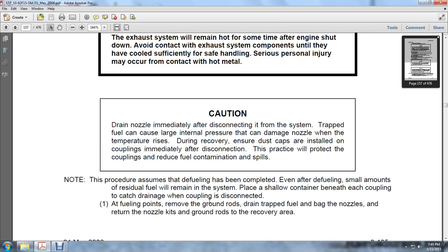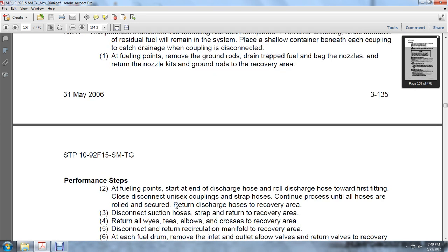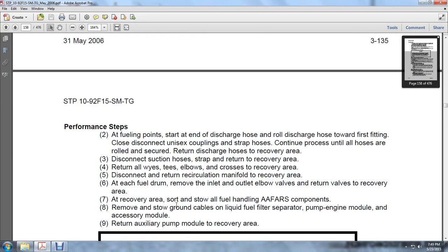At the refueling points, remove the ground rods and drain the trapped fuel and bag the nozzles. Return the nozzle kits and ground rods to the recovery area. At the refueling points, start at the end of the discharge hose and roll the discharge hose toward the first fitting. Close the disconnect unisex couplings and strap the hoses. All hoses are rolled and secured. Return the discharge hoses to the recovery area. Disconnect the suction hoses and straps.